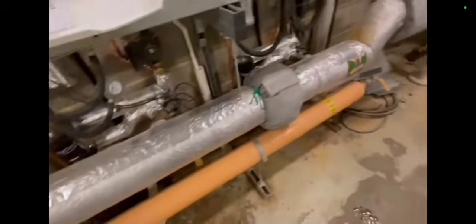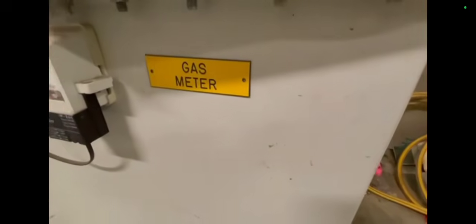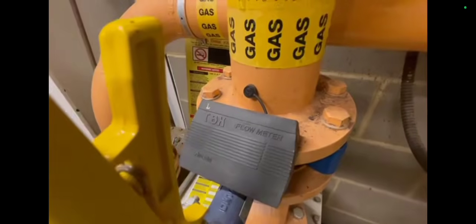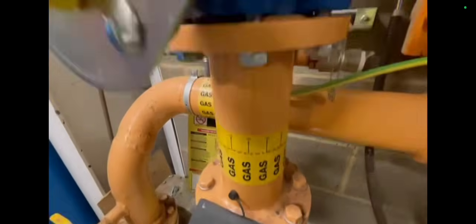Okay, each boiler has a Magna Clean on it. Alright, gas meter. We found the gas meter. It's a big one. And do remember that if it says M160, that means it's a U60 meter. Always remember that. People get confused sometimes. So that's the gas meter, a massive U60 meter. Okay, we have a flow meter, a gas flow meter there.